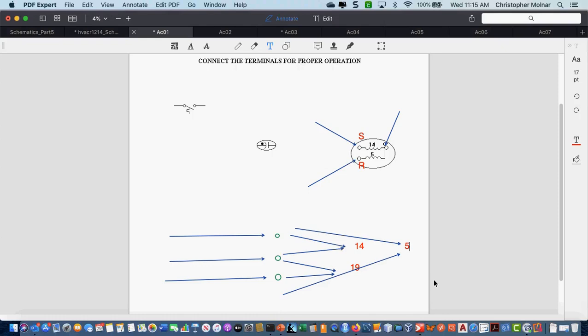Look at the motor above, the one I've labeled SR, with a pre-label of C. Do these numbers make sense based on what we're seeing on that motor up there? My resistance reading where I'm getting the 14 is between start and common. The resistance reading where I'm getting the 5 is between run and common. The resistance reading where I'm getting the 19 is actually going from start to run.